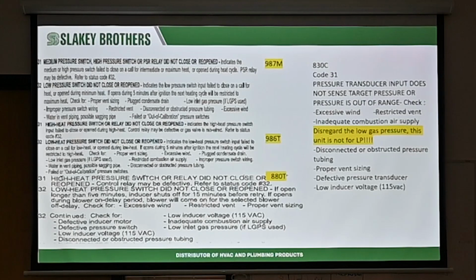Now they're making these easier compared to the older ones. They're flat out telling you negative 0.68 PF is point of failure. You're going to add 0.15 more to that. So 0.68 plus 0.15 means 0.83. This switch will not close unless the pressure is negative 0.83 or higher. If the pressure then closes and then drops below 0.68, then the switch opens. Okay? So this is where the manometer comes into play.